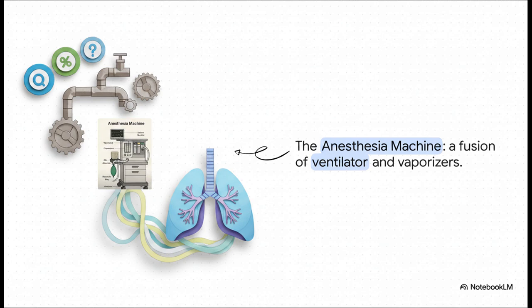The anesthesia machine is essentially the ultimate fusion of everything we've talked about so far. It is literally a master controller of both breathing and consciousness. The machine takes highly pressurized oxygen, nitrous oxide, and medical air, runs them through these incredibly precise flow meters, and then passes them through vaporizers. And those vaporizers do something that almost looks like magic. They carefully convert liquid anesthetic drugs into a perfectly breathable gas at perfectly precise concentrations.